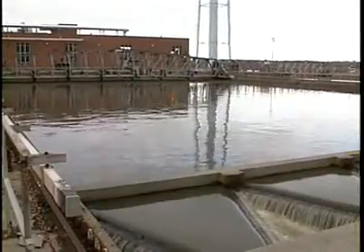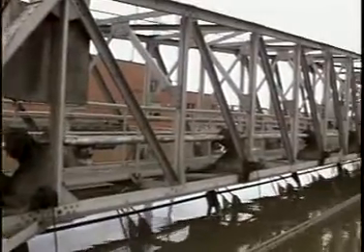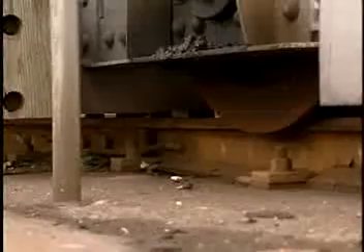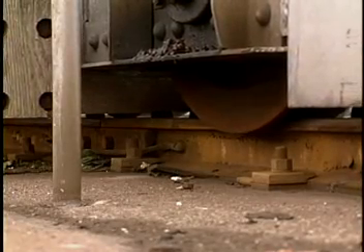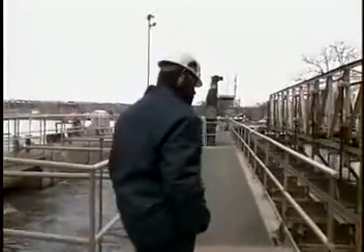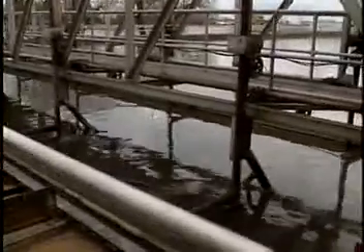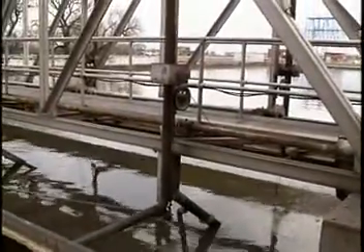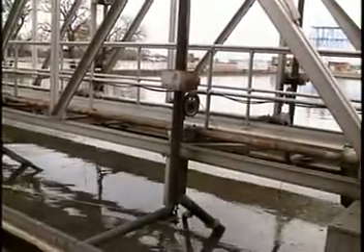This is one of twelve primary settling tanks. The bridge across it moves slowly from end to end. At the moment, it's on its way to the input end of the tank, using a rubber blade to skim grease on the top into a conveyor. It dwells here for about six minutes. On the ride back, the bridge's underwater scraper wipes settled sludge off the bottom of the tank.